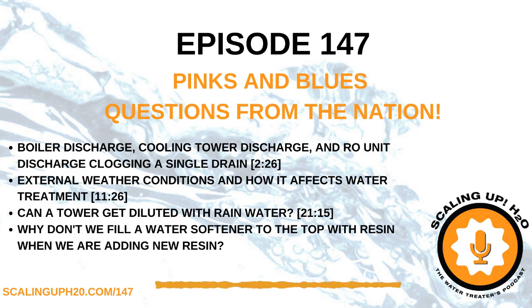Now, some people might say, well, I can program those particular pieces of equipment to only bleed at certain times of day. But we know boilers and cooling towers are always running, and we bleed so we can dilute the solids in the system so we don't create a scaling situation. So if we tell it not to bleed for an extended time, we could exceed the limits on our scale ions. We have to consider that, and that probably isn't an option for you.